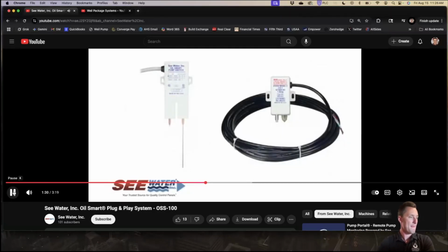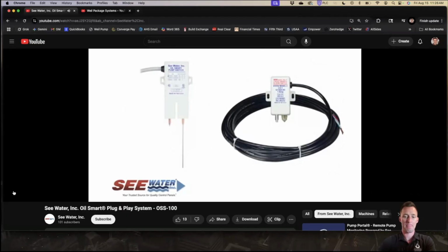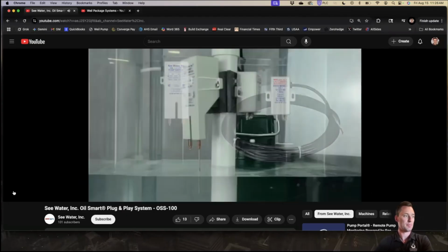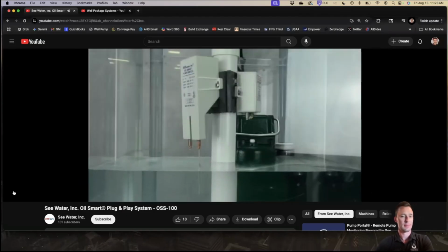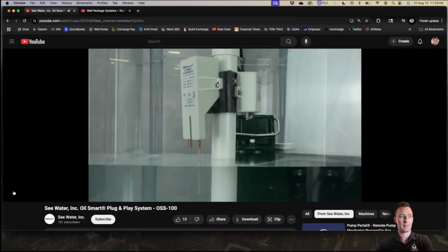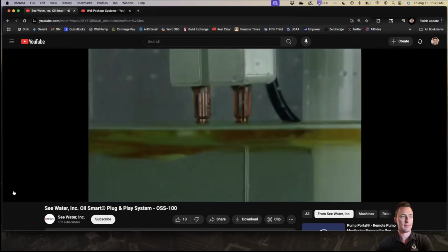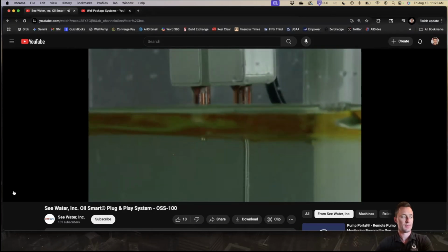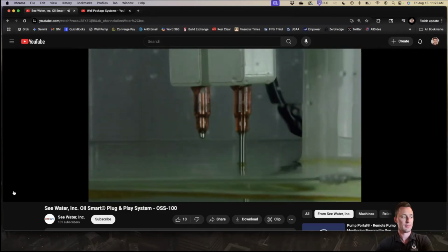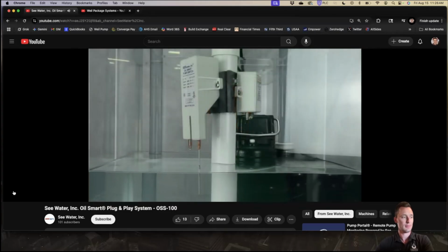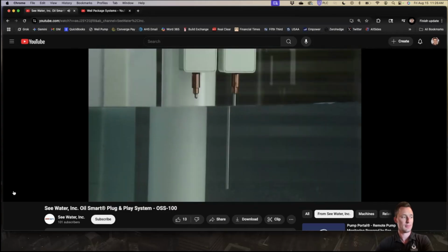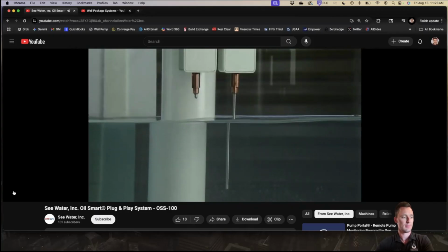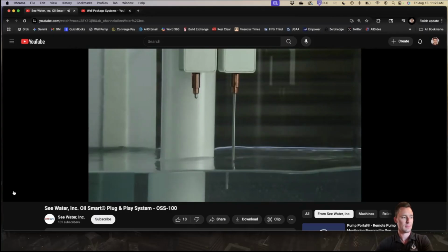All systems include the Oil Smart switch and Liquid Smart alarm technology. The Oil Smart switch is an IP68 rated reliable and durable oil-water switch. It includes two sensors. When water comes in contact with the on sensor, the pump will turn on and remains on until the water clears the off sensor. During normal operation, water will make contact with the on sensor and pump the water just below the off sensor.